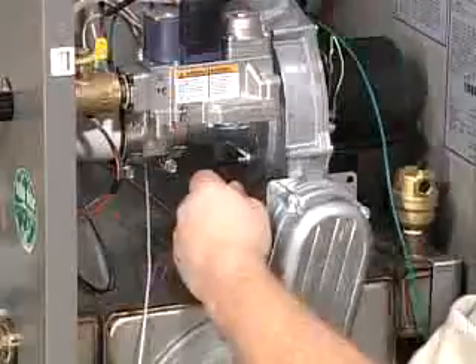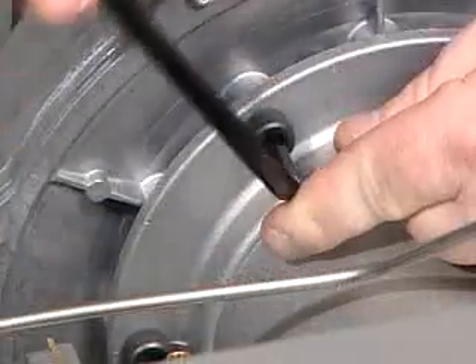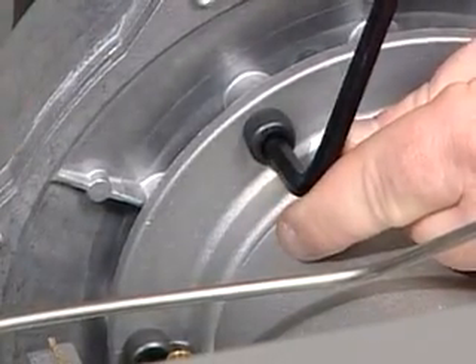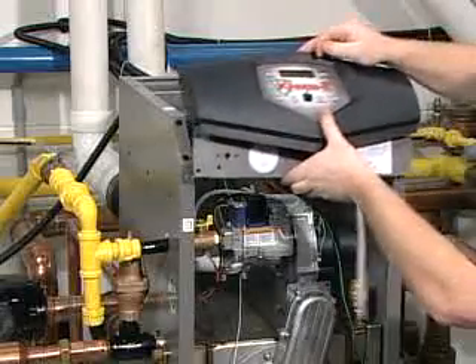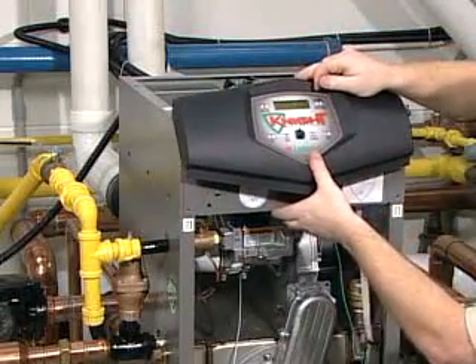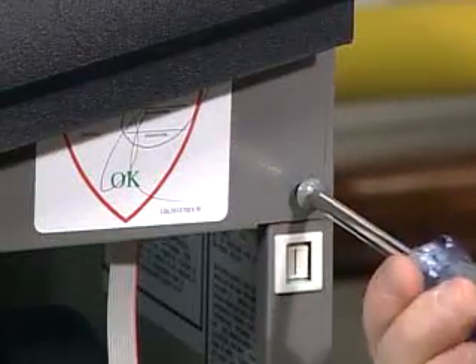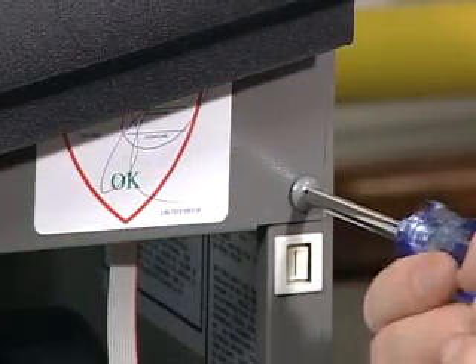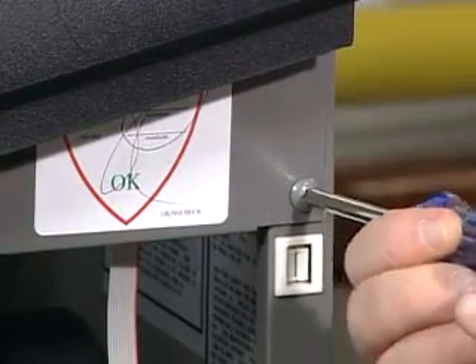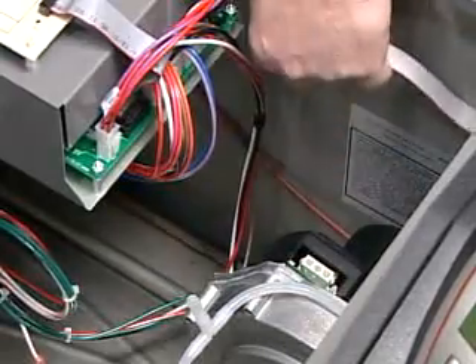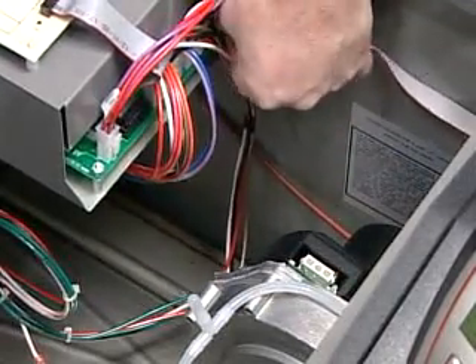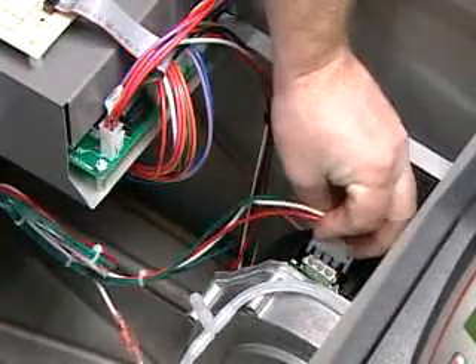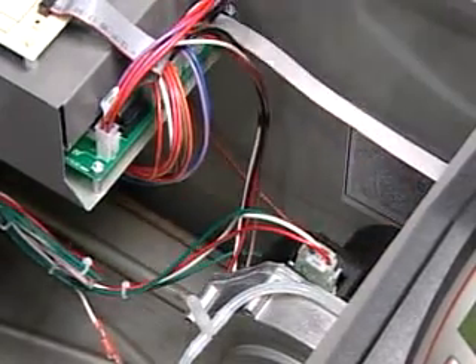Install and tighten the screws securing the gas valve venturi to the inlet of the combustion blower. Replace the bezel on the front of the unit. Install and tighten the 6 screws securing the bezel to the unit. Reconnect the ribbon cable from the display to the main control board. Reconnect the 2 wiring harness connections to the combustion blower.